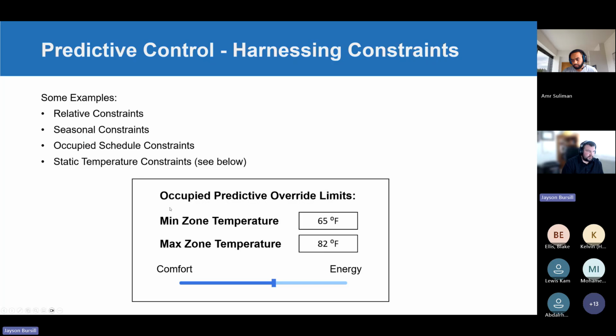So being able to put the real override limits, which in this case I've used halfway between the occupied and unoccupied set points prescribed by ASHRAE Guideline 36, and then just a basic slider that manages the cost function between thermal comfort and energy—this is ultimately the type of interface I think is required to do more complicated algorithms, even at the zone level, in a way that can be administered and have a level of trust, which gets to this AI constraints thing, where constraints are very important, along with some sort of input and feedback to the system.